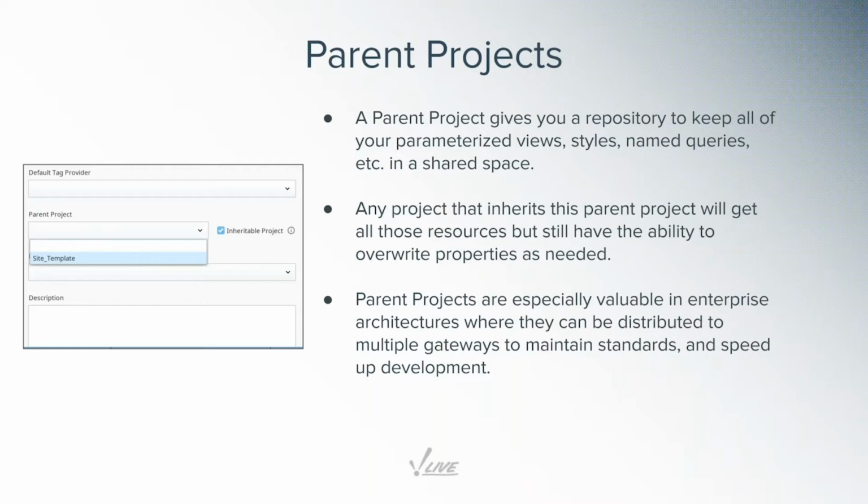So you're not stuck with only using it as it's defined in the template, but you can also customize it. And it's great because a parent project works on a single gateway, but you could also move that parent project to other sites in an enterprise architecture, and all those different sites could inherit these same templates. So you maintain consistency and standards between all of your sites. And so parent projects are huge.